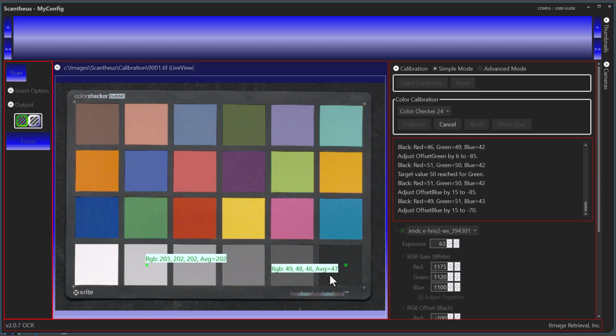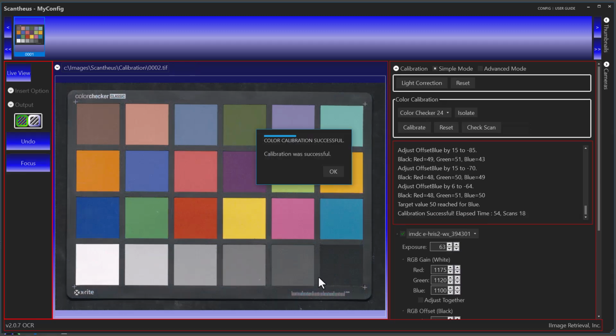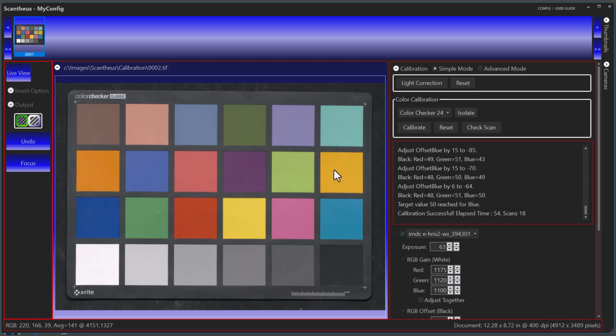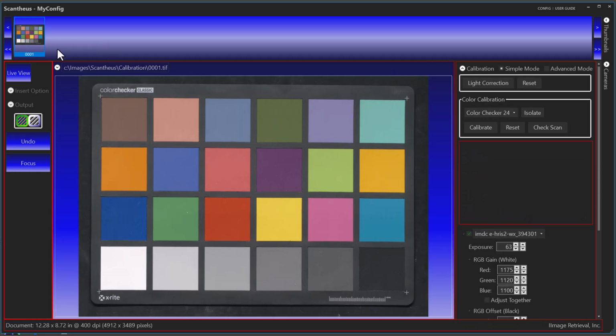So what it's doing, it's taking a scan and analyzing that patch every time, and then adjusting the setting as needed to get to the target area. Our calibration is successful. So it took 54 seconds, 18 scans, and it always does a scan at the very end of calibration. So you can take a look at the image here. We're going to look at the black patch. If you look at the bottom left, it shows the RGB value of the patch, or the area that we're highlighting there. Our target there is 50.